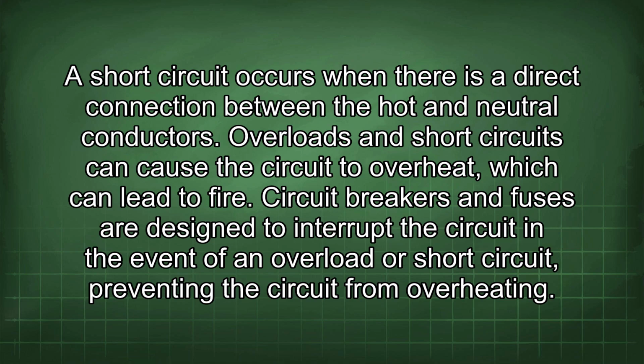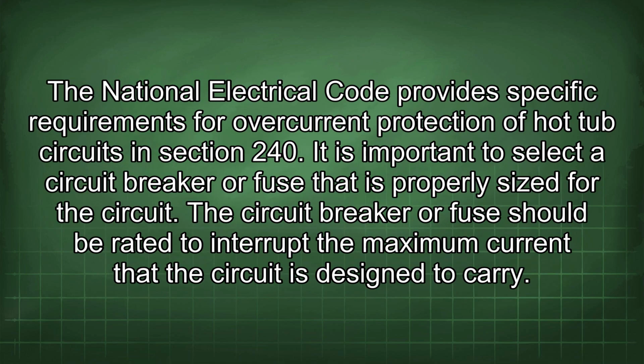the circuit from overheating. The National Electrical Code provides specific requirements for overcurrent protection of hot tub circuits in Section 240. It is important to select a circuit breaker or fuse that is properly sized for the circuit. The circuit breaker or fuse should be rated to interrupt the maximum current that the circuit is designed to carry.